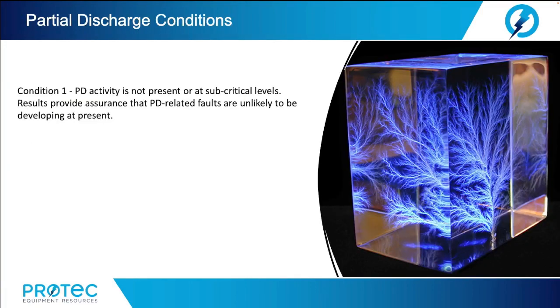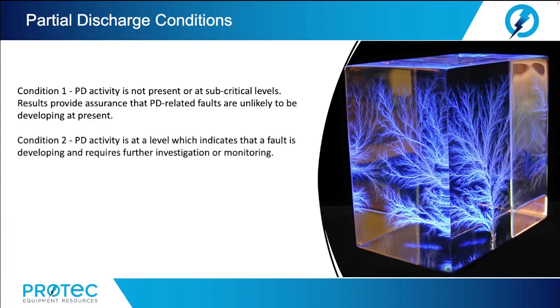All right, next let's talk a little bit about partial discharge conditions. For instance, condition 1: partial discharge activity is not present, or it is at a subcritical level. The results provide assurance that partial discharge-related faults are unlikely to develop at present. In condition 2, partial discharge activity is at a level which indicates that a fault is developing and requires further investigation or monitoring.